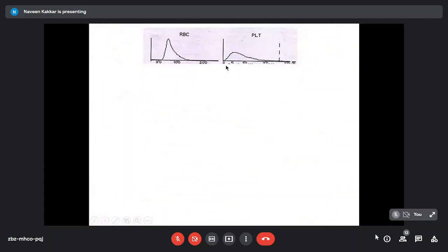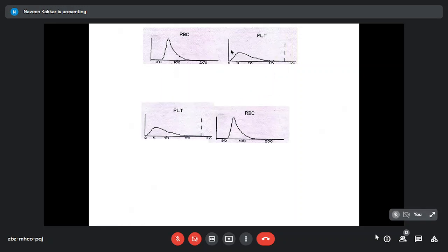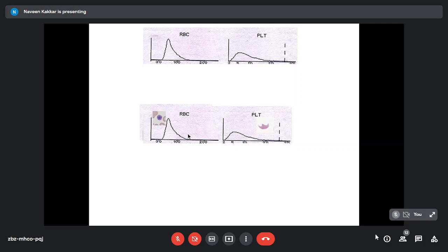Remember, in the last talk we looked at this histogram. The platelets and the RBCs are actually counted together, and that's how it's generated within the instrument. Volumes less than 20-25 are counted as platelets and higher ones as red cells. So in this patient, what happened? Your red cells fragmented because of burns, and they cause volumes lower than 30, which fell into the platelet zone. So the platelets were counted more than normal. Here your red cell fragments are being counted as platelets.